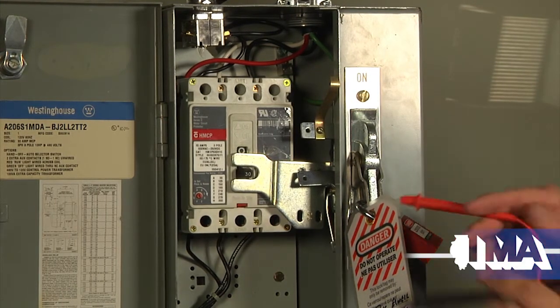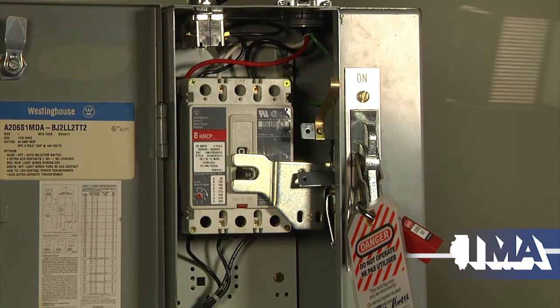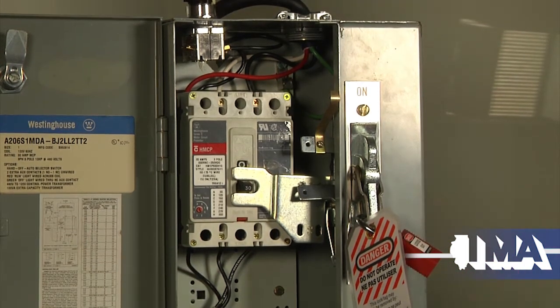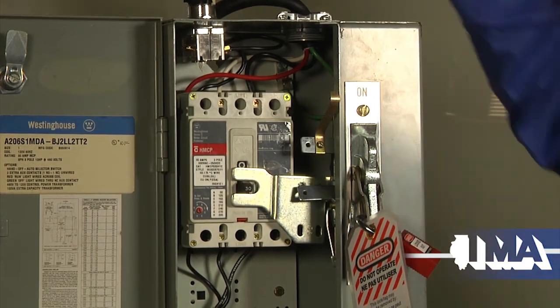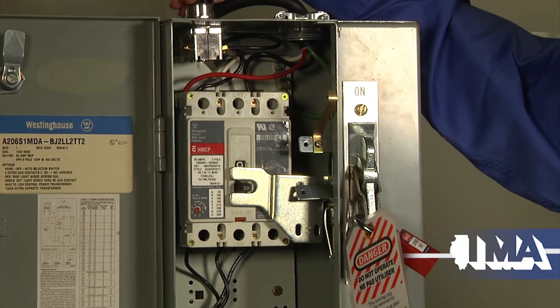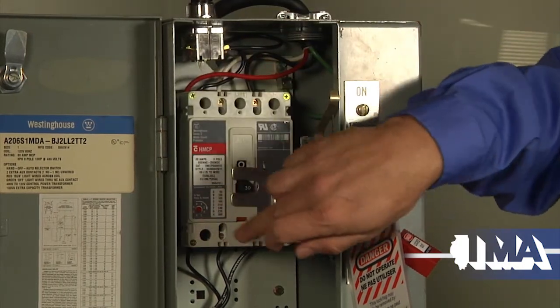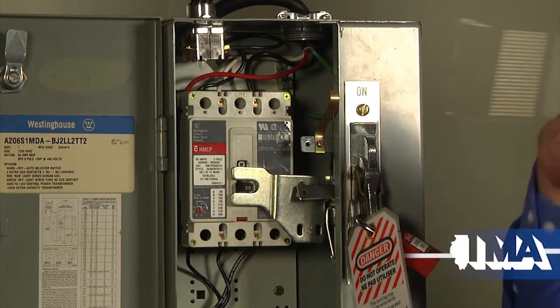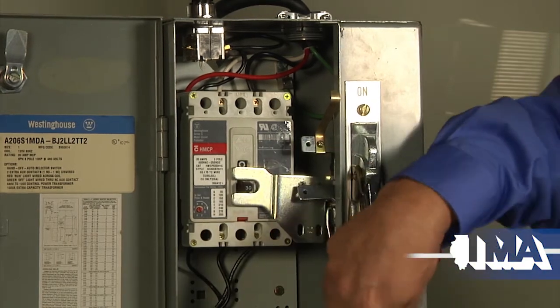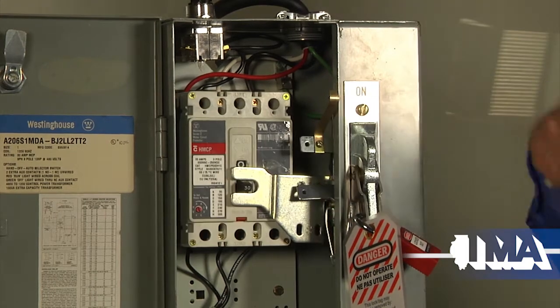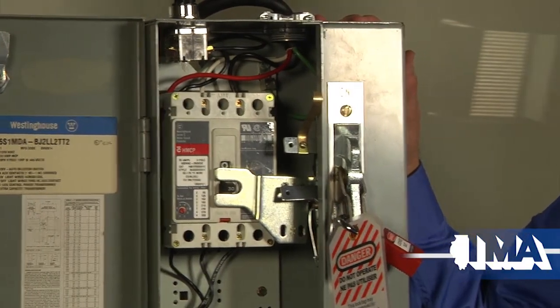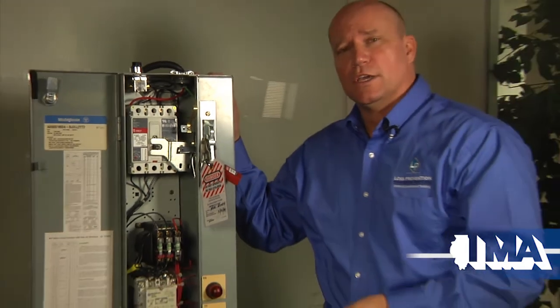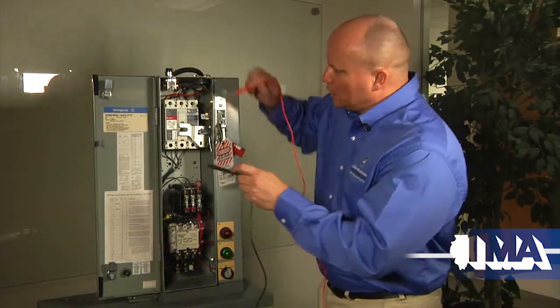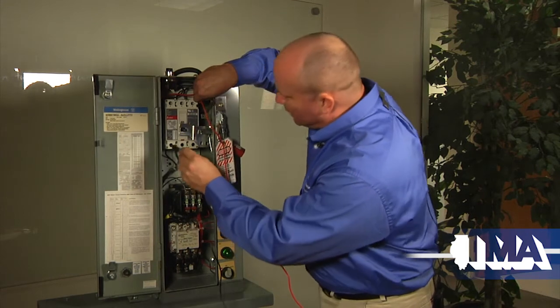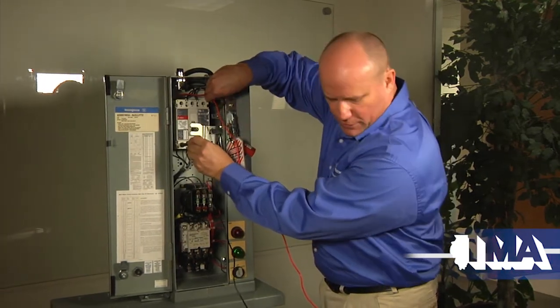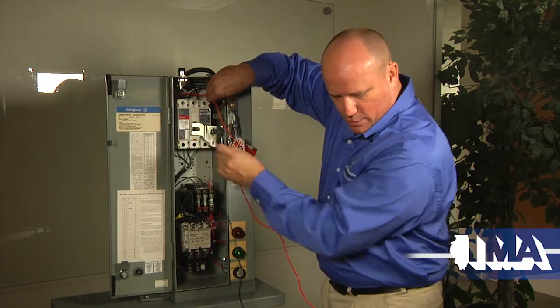And there's a reason for that. If I just verified all 3 phases together, or all 3 points, and I walked away, there could actually be power in there. For training, I have a switch here that would simulate a stuck phase. And in fact, we'll show you the schematic. If you go through the transformer, the voltage at that point through the transformer is the same as that point. So if I'm doing a phase-to-phase check, I'm checking a difference in potential. Since it's the same phase, same voltage, you're not going to get a difference in potential. So the phase-to-ground points are really important in this case. I check A to ground, I verify 0 volts, B to ground, get the meter.